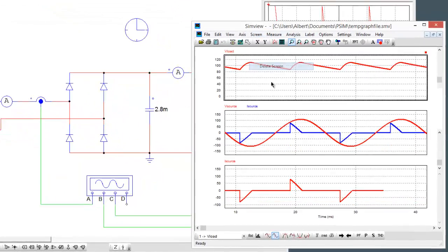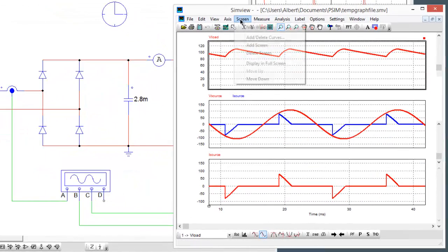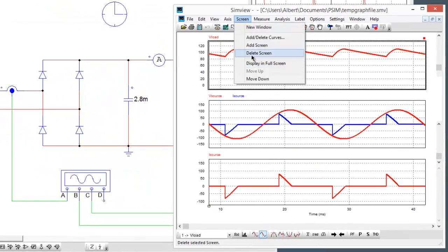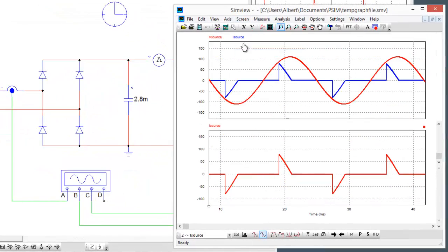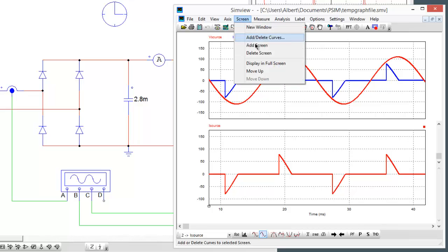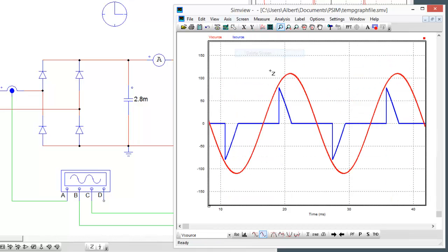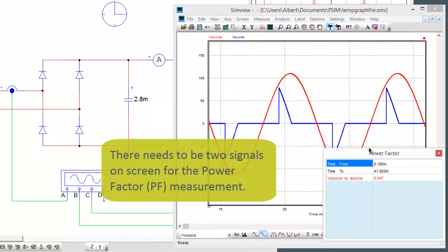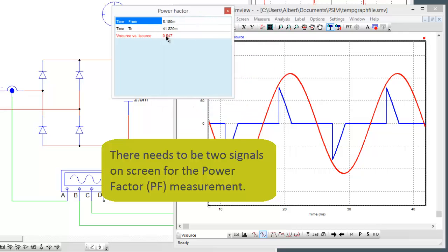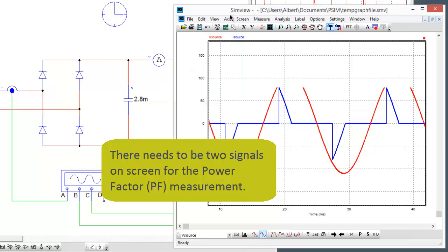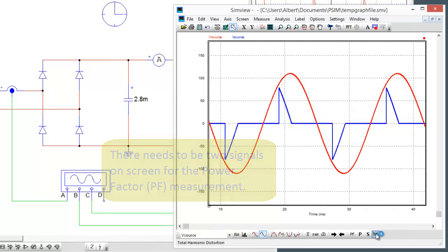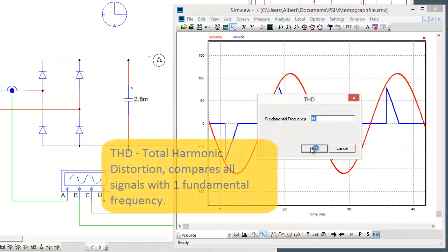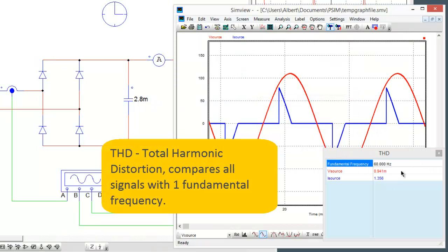Let's do power factor. We're seeing a power factor of 0.54, and now also we can pull up is THD on the fundamental. We can see the source voltage is pretty much ideal and the current is sort of off the charts.